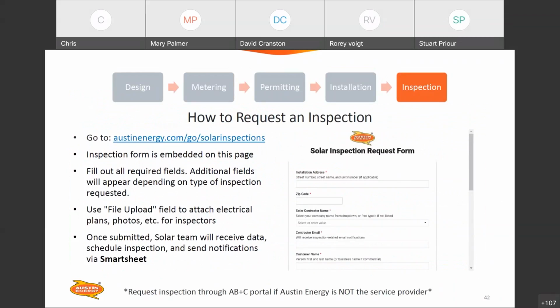Joel is asking, does AE approve breaker interconnections without a main breaker and with the 6-handle rule, or do all generation interconnections require a main breaker? Yes, you've got to have a main breaker - Austin Energy doesn't approve an interconnection without one. And the 6-handle rule has morphed a bit in the 2020 code cycle: you can still have 6 disconnects, but they need to be in each of their own separate enclosures, so the 6-handle rule within one panel is no longer adequate. The line side tap or backfeed breaker has got to have a main on it into the meter.